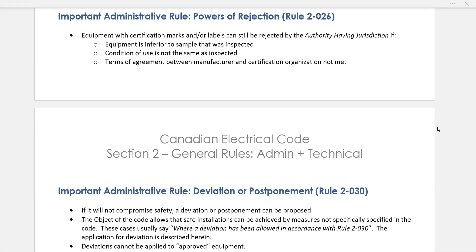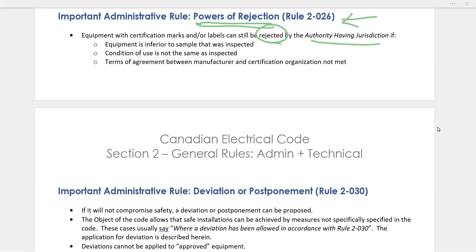Let's talk about two more administrative rules in Section 2: Rule 2-26 and Rule 2-30. Rule 2-26 is called Powers of Rejection. Even though there is evidence of approval on equipment — a certification mark, a special inspection label, or a field certification label — it can still be rejected by the AHJ, the Authority Having Jurisdiction. It can be rejected if they determine that an inferior sample was actually submitted for the certification mark.